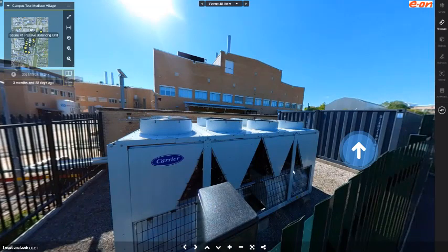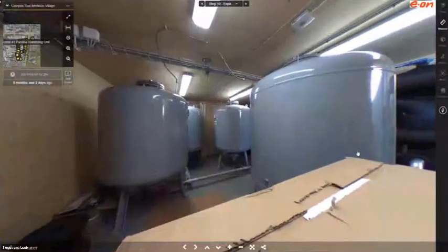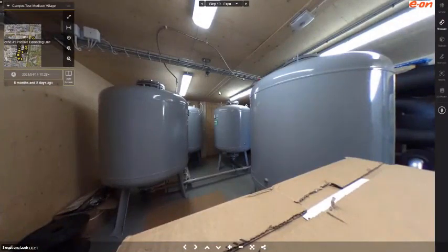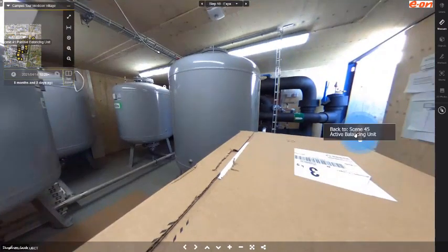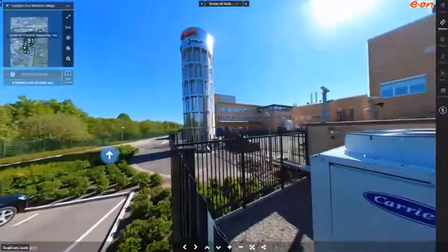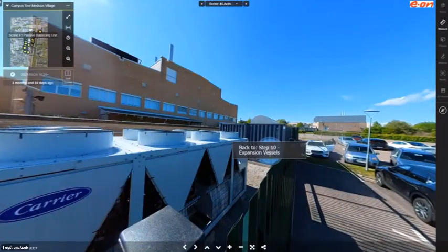So when we have too much heat in the system, we can expel heat using these into the air. The opposite goes if we don't have enough heat inside the Ectogrid system - we can retrieve heat from the air and push it into the Ectogrid system. To be able to use a pressured system, we also need these expansion vessels, situated in these gray containers in between the 2 heat pumps.